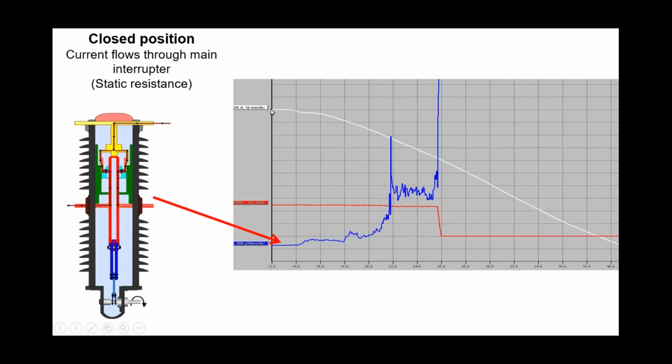And what you have in white, just to show you what stage in the operation we are in, is the motion curve. If you look at the timing, we started the analysis at 12 milliseconds, not at 0. Practically between 0 and 12, the curve will be identical with the first part described here. No variation of the current or resistance.